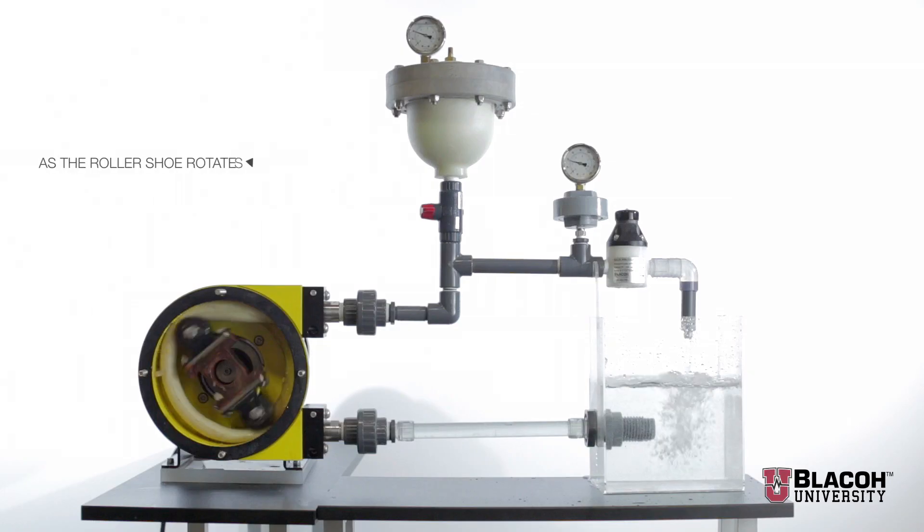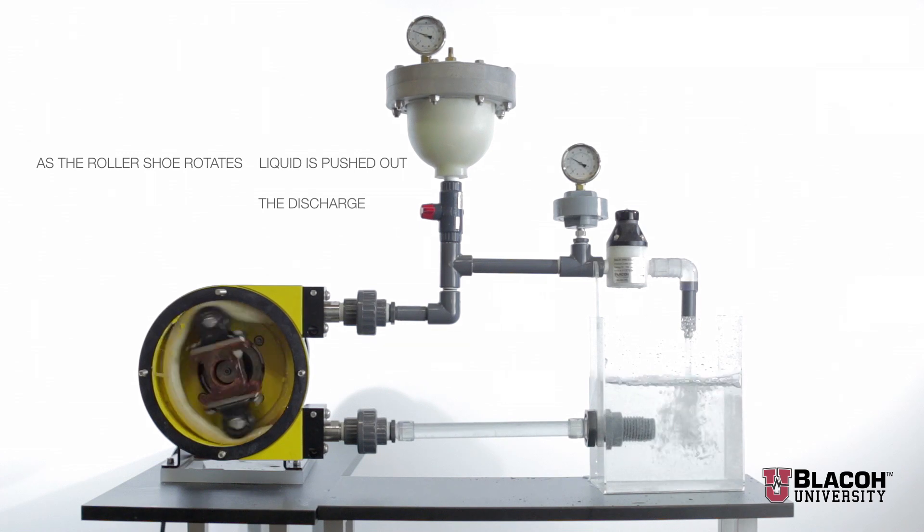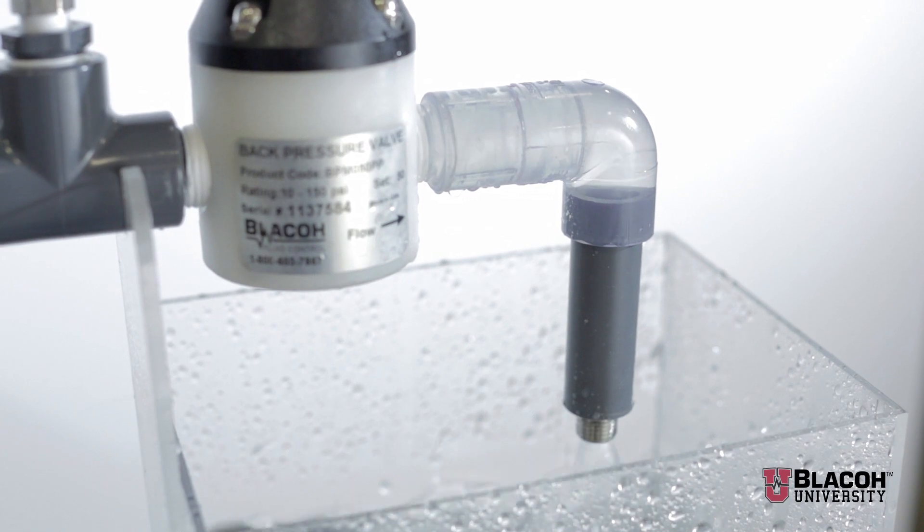As the roller shoe rotates, liquid is pushed out of the pump's discharge. When the roller shoe releases the hose after discharge, a momentary void or pocket is created where there is no product. This creates a partial vacuum as some product is actually sucked back to the discharge momentarily.